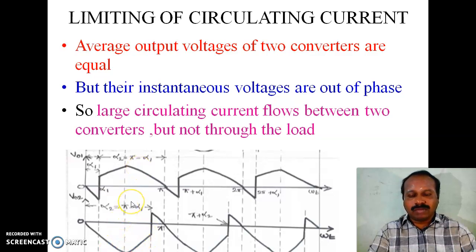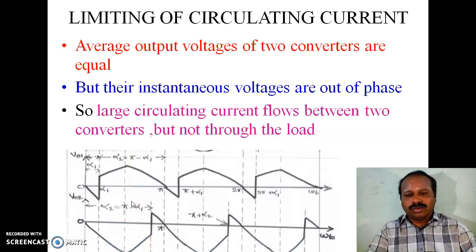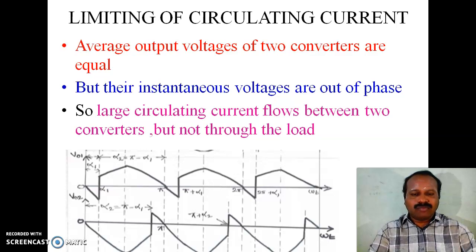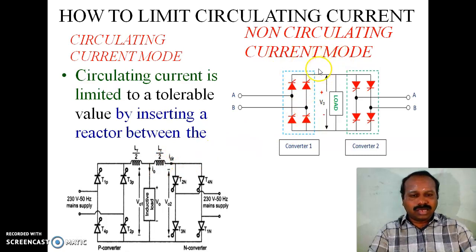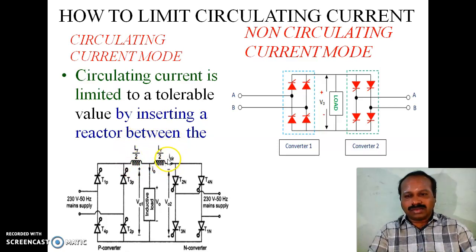The instantaneous values are different but the average values are the same. So a large circulating current flows between the two converters, but this circulating current does not flow through the load. To limit this circulating current, unlike non-circulating current mode which has no reactor, here a current-limiting reactor is inserted between the converters. The circulating current is limited to a tolerable value by this circulating current reactor.